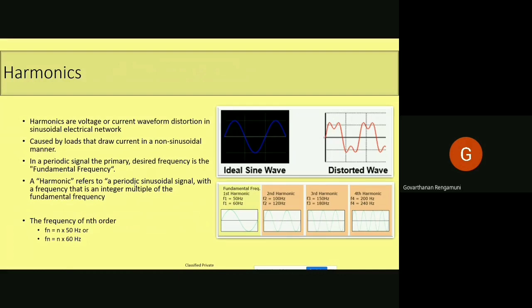Coming to the harmonics, let us discuss in detail what harmonics are. You can see the various waveforms kept here. Look at the top two waveforms. One is the ideal sine waveform. The second is the distorted waveform. Generally, if a sinusoidal voltage is applied to a resistive load, the current will also be sinusoidal. But when the sinusoidal voltage is fed into a nonlinear load or a power converter, the shape of the current will not be sinusoidal; it will get distorted. For example, the waveform will look like the distorted waveform shown in this slide.